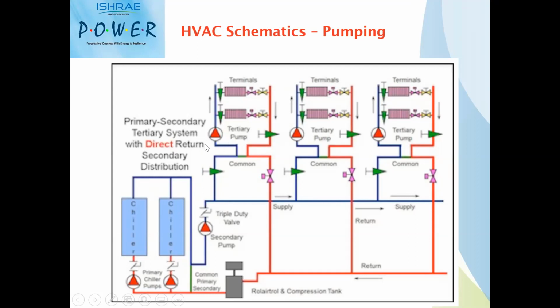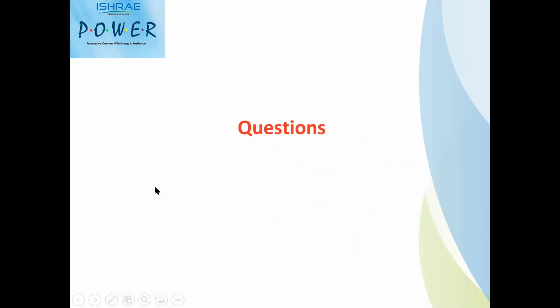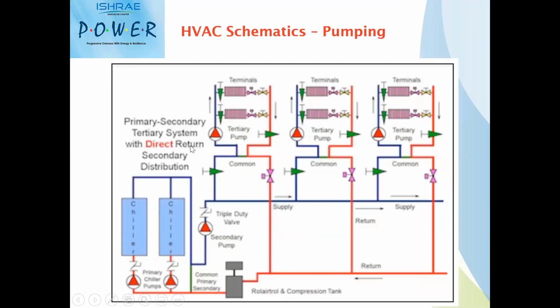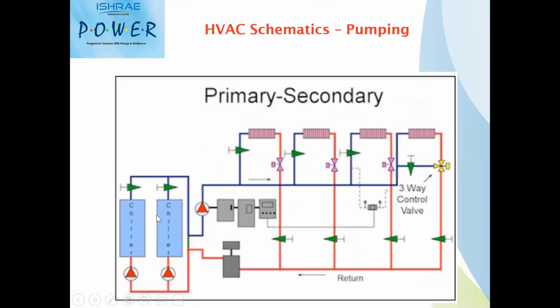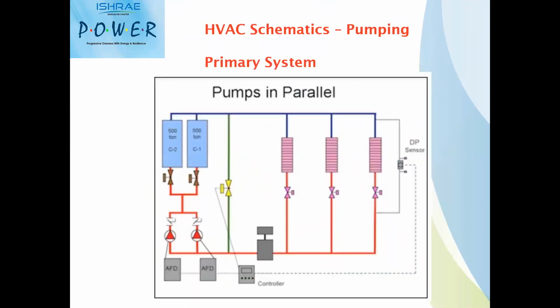Maybe a heat exchanger is used in between, or directly coupled, or in some cases the secondary is eliminated and only primary and tertiary pump circuit may be designed, where primary will cater the water to the PHEs or the distribution side pumps, and from there typically the pumps distribute water to the load side and it comes back to the primary side. So whenever we are selecting pumps for a typical primary, or primary-secondary, or primary-secondary-tertiary application, it all depends on your type of the building.